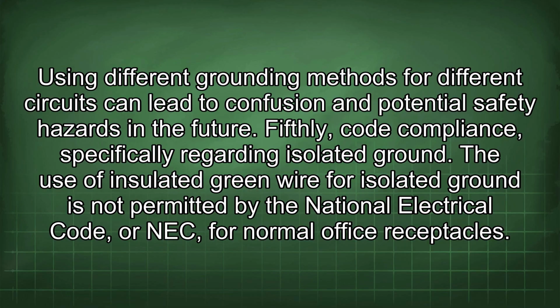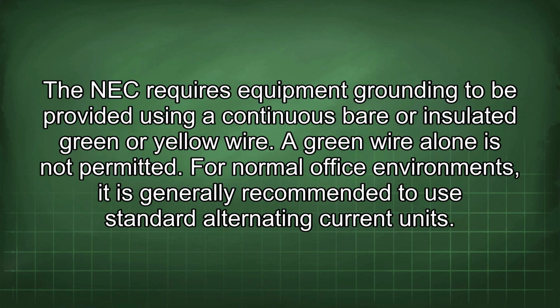Fifthly, code compliance, specifically regarding isolated ground. The use of insulated green wire for isolated ground is not permitted by the National Electrical Code, or NEC, for normal office receptacles. The NEC requires equipment grounding to be provided using a continuous bare or insulated green or yellow wire. A green wire alone is not permitted.